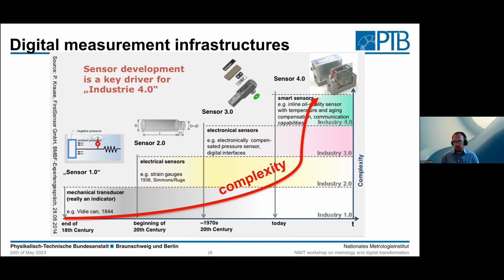So far, so good. But as soon as you take the instrument and put it in an existing traditional calibration environment, you may see very strange behavior because maybe the software engineer wasn't aware of the way you do the calibration. You as a metrologist don't have access to the actual raw data, but only to the process data. And then you may end up with a situation of a very, very complex measuring instrument, which calls itself a smart sensor, but seems to be very dumb in the sense that it behaves very strangely. So there's an increasing complexity because the software adds to the already existing and evolving complexity of the instrument itself.